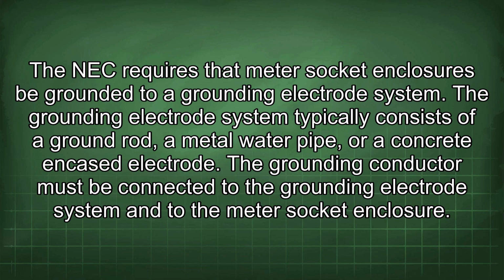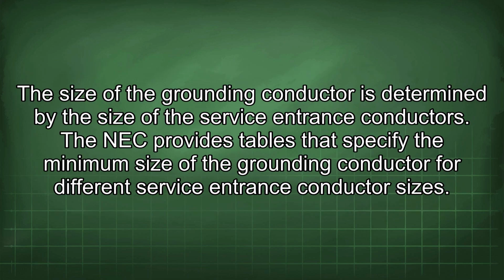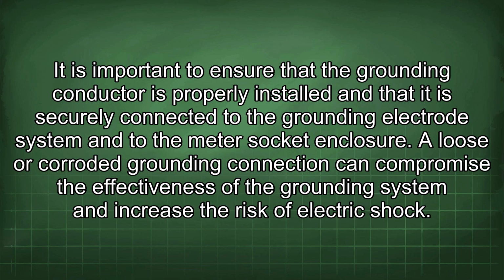The NEC requires that meter socket enclosures be grounded to a grounding electrode system. The grounding electrode system typically consists of a ground rod, a metal water pipe, or a concrete encased electrode. The grounding conductor must be connected to the grounding electrode system and to the meter socket enclosure. The size of the grounding conductor is determined by the size of the service entrance conductors. The NEC provides tables that specify the minimum size of the grounding conductor for different service entrance conductor sizes. It is important to ensure that the grounding conductor is properly installed and that it is securely connected to the grounding electrode system and to the meter socket enclosure. A loose or corroded grounding connection can compromise the effectiveness of the grounding system and increase the risk of electric shock.